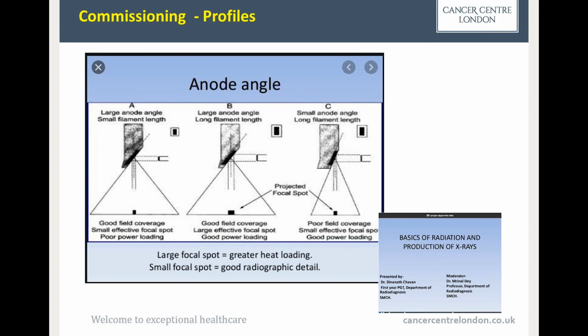If you look here, you can see that for a big focal spot size, we can get quite good coverage of the field that we are interested in. It means that in radiotherapy, we are interested in good coverage of the radiation field. But the most important thing is that the angle of this anode is chosen in such a way that part of the radiation which goes from the anode side is not interacting with the anode material, so that the coverage is not decreased, and we can see this like a wedge effect. If you look very carefully at this moment, we can say that solution B is representing an X-ray tube for X therapy.